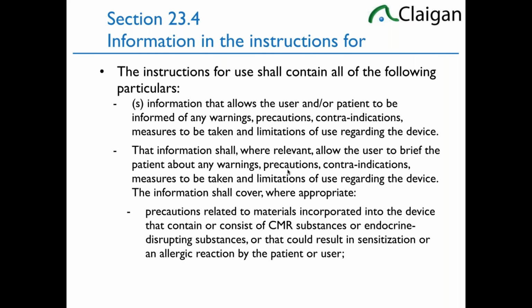So these are sensitizers. There's also respiratory sensitizers. Now, it's more of a problem if your product is a dust or airborne. That's usually not really a problem in most physical medical devices, but you're definitely looking at allergic reaction. If you make wearable devices or more consumer devices, the number of materials that can have the potential for sensitization goes up, often due to prolonged contact. If it's a wearable, some kind of blood pump or other measurement device that stays on, or implantable device, sensitization is a big deal.